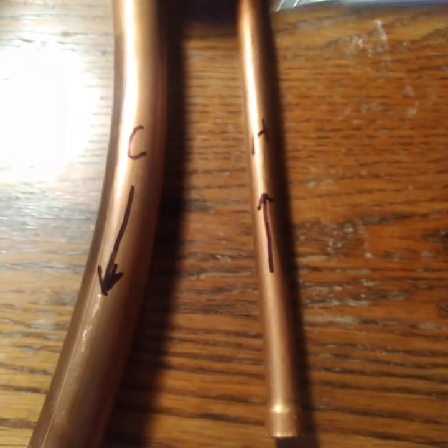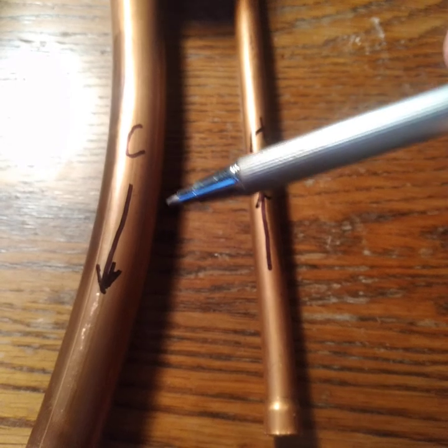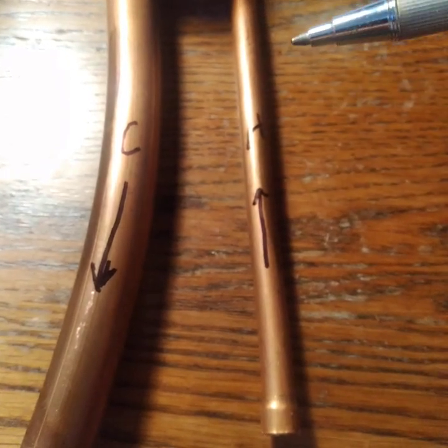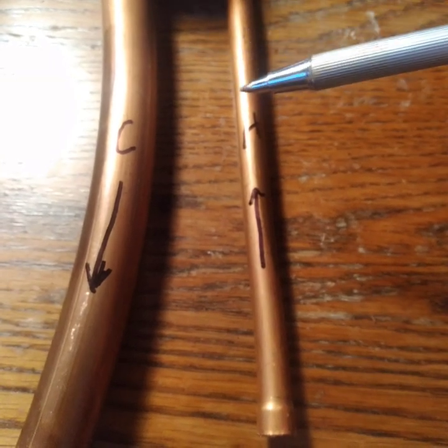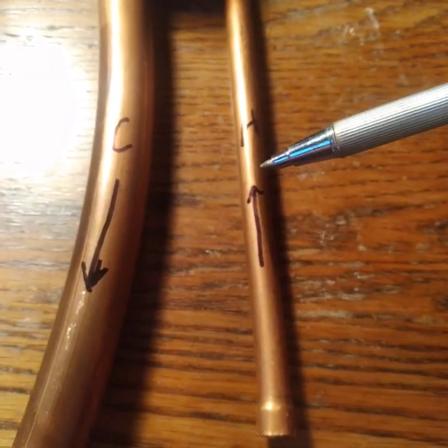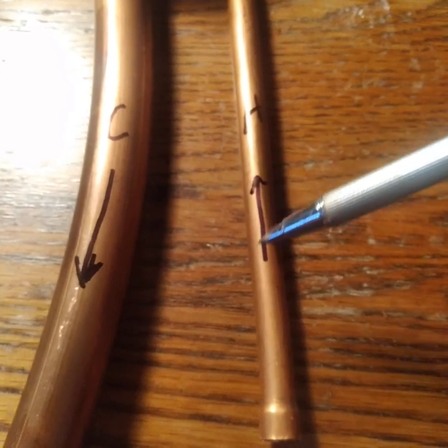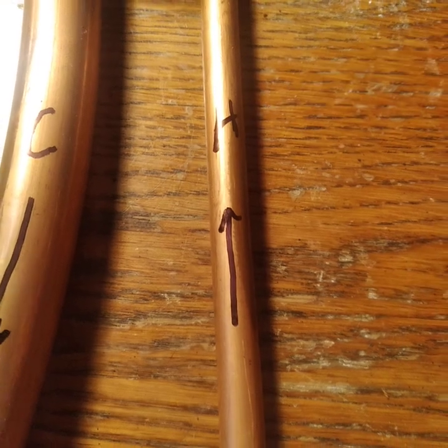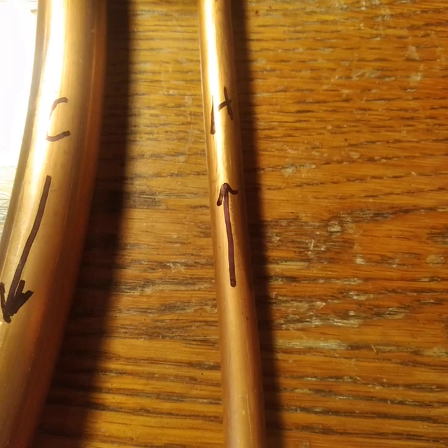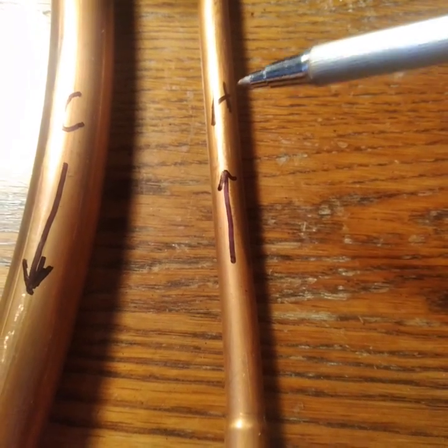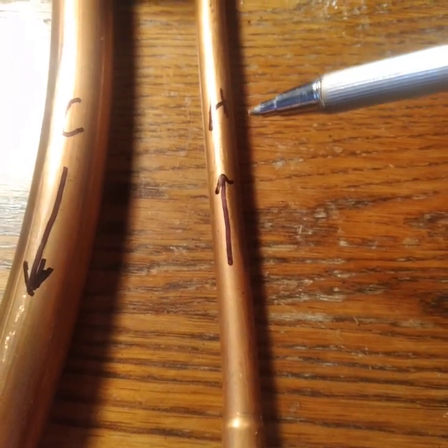At this point, the cool air comes across if the fan motor's working and everything's working properly, and the high pressure vapor starts to condense. Then it comes out in this small pipe, which we've labeled hot or warm. It's generally warm. One can touch it. Sometimes when it runs fairly hard in the summer months like July and August, it can get a little bit hot to the touch. So we'll say hot or warm.